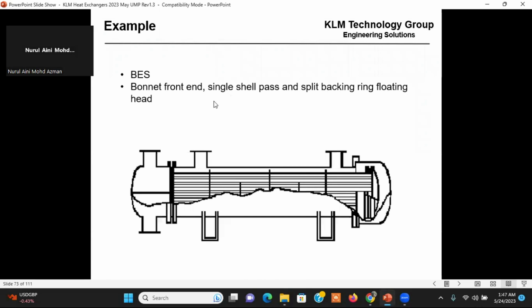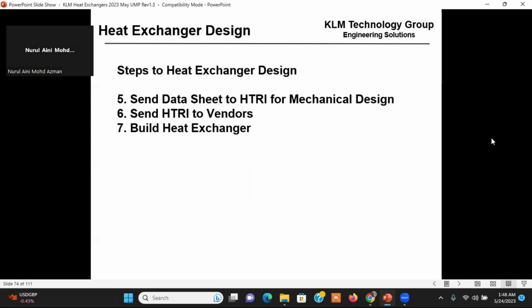There's a BES. So it's got a B on the front, and it's got a floating head in the back. So you can pull it out. You can take this back end off, and you can clean. All right. When you pull it all the way out, you actually clean the outside of the tubes. So I can take this back end off. I can clean the inside of the shells. After I pull it out, I can clean the outside of the tubes. All right. So this is an okay design. BES is okay. BEM is okay. So that's typically what I use.